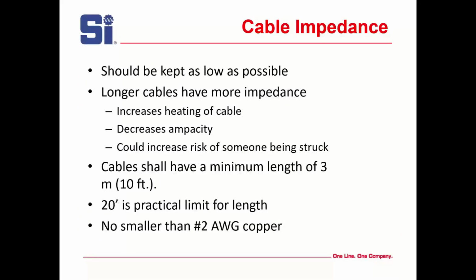Cable impedance really has to be as low as you can make it. Longer cables have more impedance. That's why ASTM F855 tells you 10 foot. That's the shortest it should be. And what they don't say is, in discussions I've had with the committee and with utility people who use personal protective grounds all the time for their lines, they say 20 feet is about all you can go. You go above 20 feet, the impedance really gets kind of nasty. And that's going to decrease the capacity and could risk someone being struck by it whipping. I know you've probably been on YouTube, seen a lot of short circuits on grounds and how they whip. You don't want to be there.